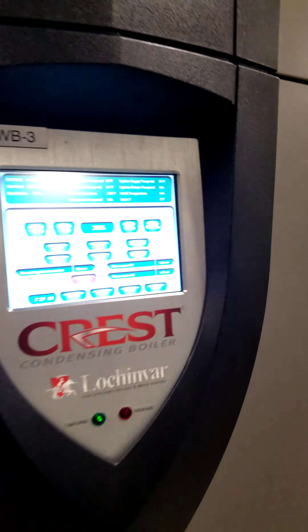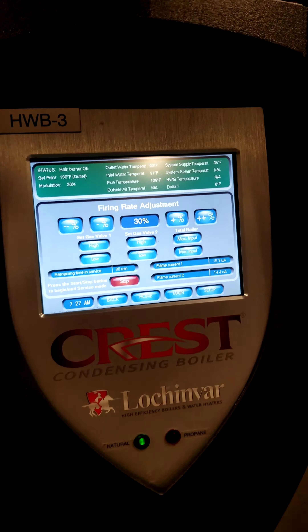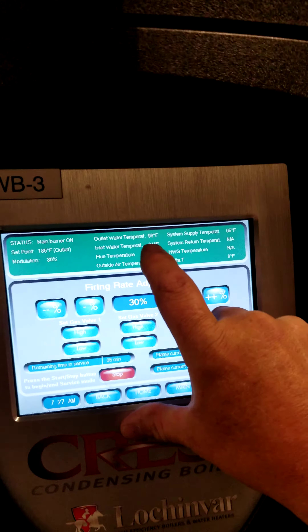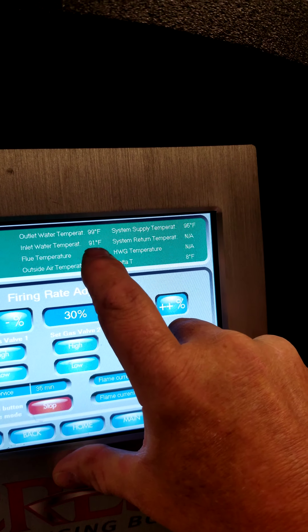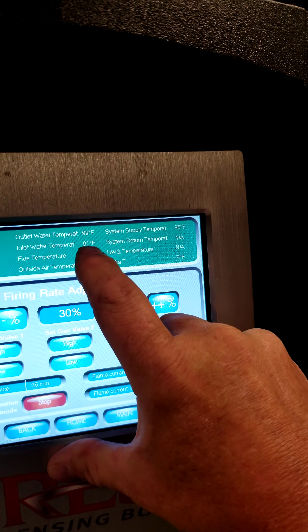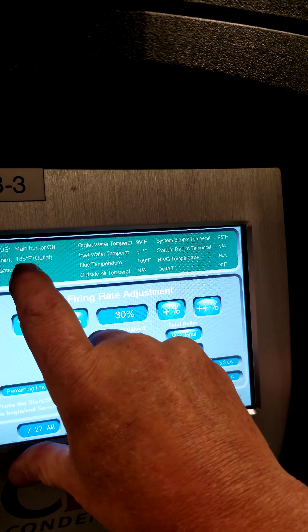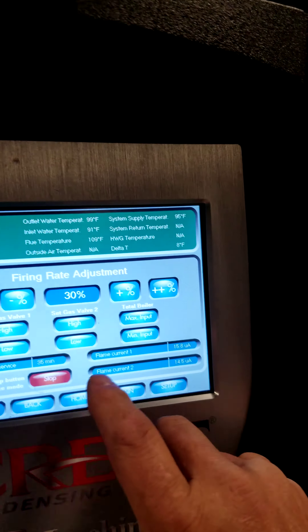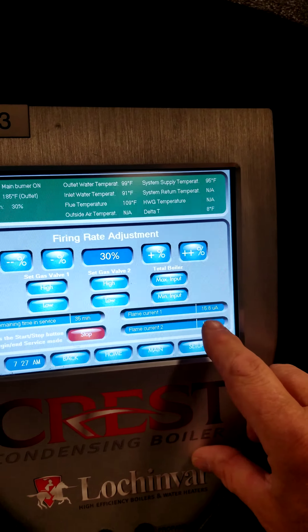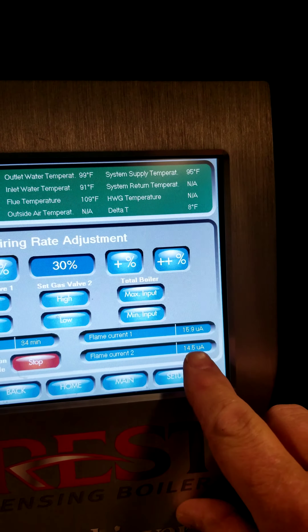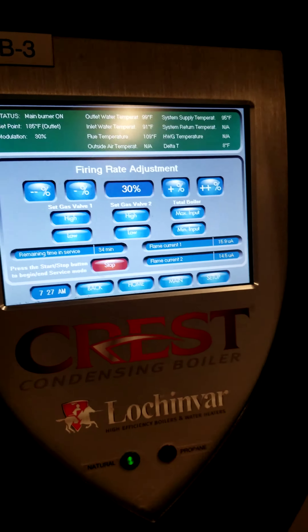So I came back over to boiler three and started it to get the temperature warmed up. Notice this is what our water temperature is coming back from the building — 91 degrees. It's not enough. This is the set point. I have this one started and running; I've got these two burners on.